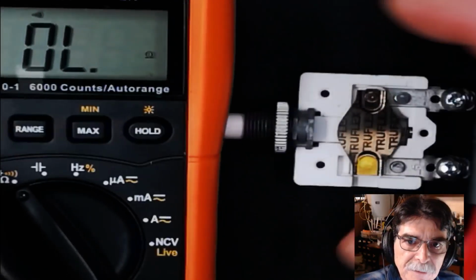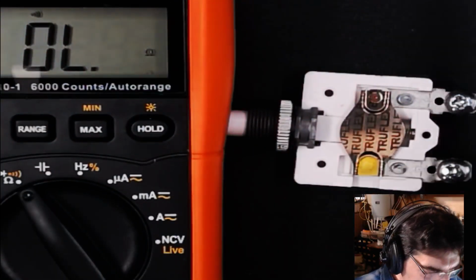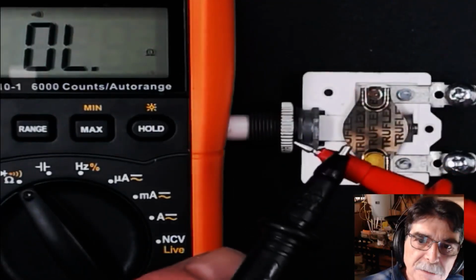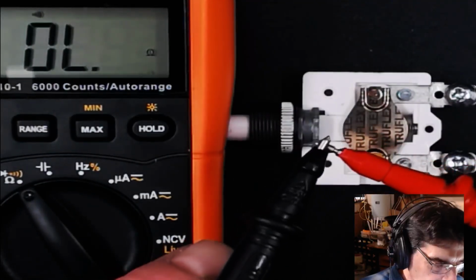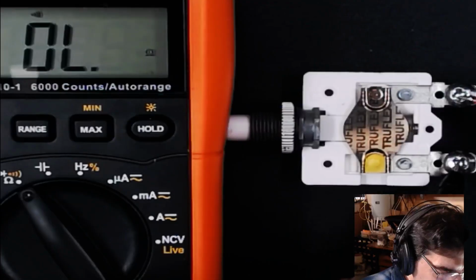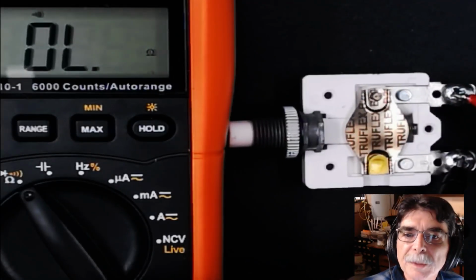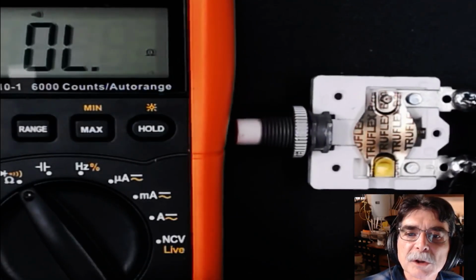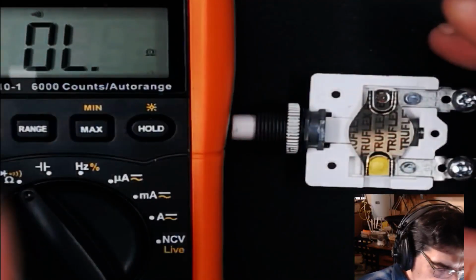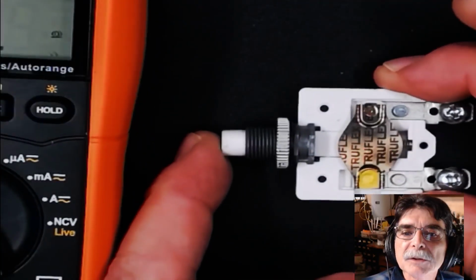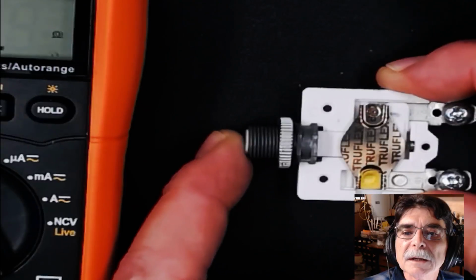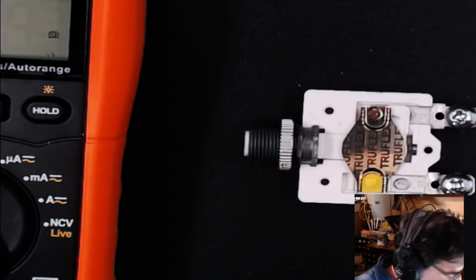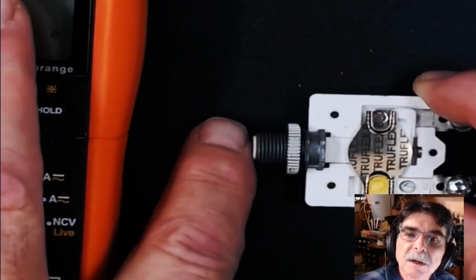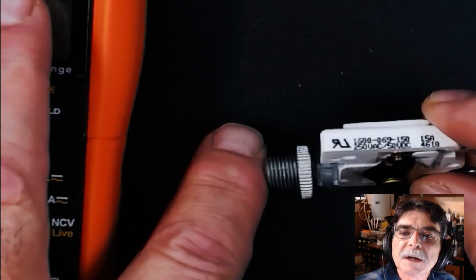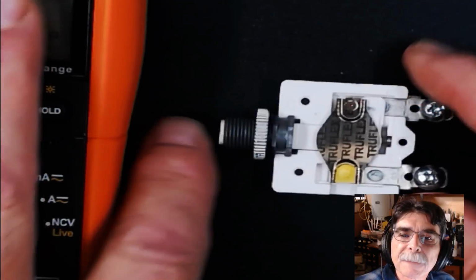circuit breaker. We're going to take our probes, short them again, make sure we're in continuity, and put them on these screws. And it is open, because the circuit breaker is tripped. To reset it, you just push this in, click, and you see this device here, which is kind of a guard. It is what obstructs the contacts on a circuit breaker.